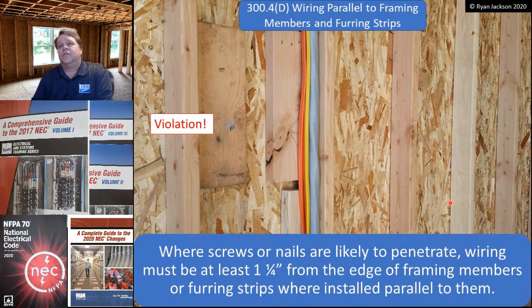Wiring that's parallel to framing members and furring strips. So 300.4(A) talks about it perpendicular when we drill holes through the furring strips. And then (B) talks about metal. And then subsection (D) says where screws or nails are likely to penetrate, wiring must be at least 1 1/4 inches from the edge of framing members or furring strips where installed parallel to them. What we're looking at here is a violation.